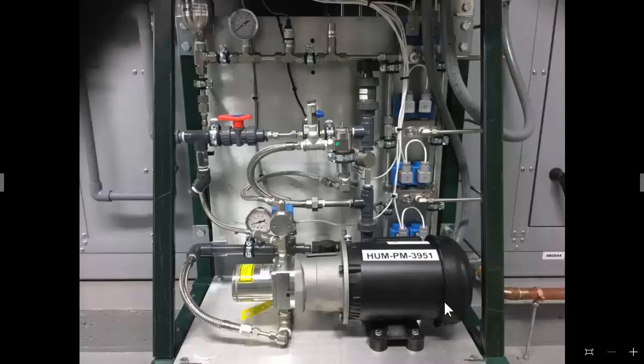Now, similar to the input piping, this has got a pressure transducer. This one right here. It's got a discharge pressure gauge right there, and then it's got a relief valve right here. So we're going to cover those. And this pressure transducer, like I talked about on the input side, there's a couple of differences here. One, this is a 0 to 2000 psi gauge, and typically we're running at between 600 and 900 psi. So 0 to 2000, and the output signal is 1 to 10 volts. That corresponds to that 0 to 2000 psi.